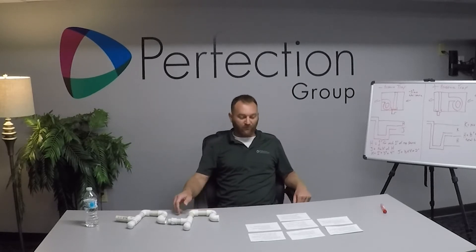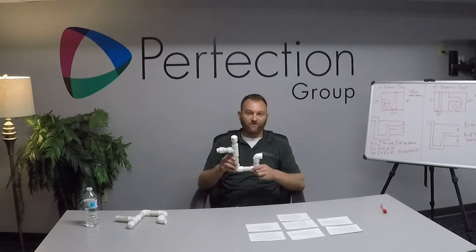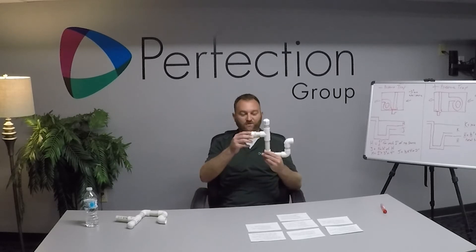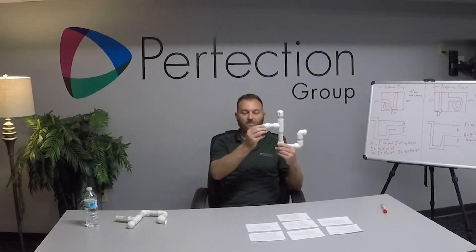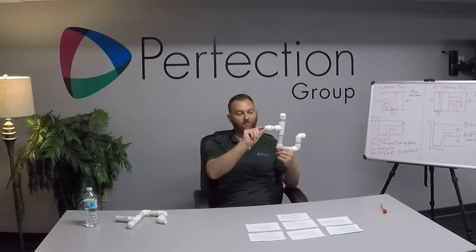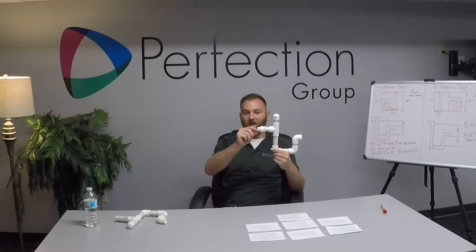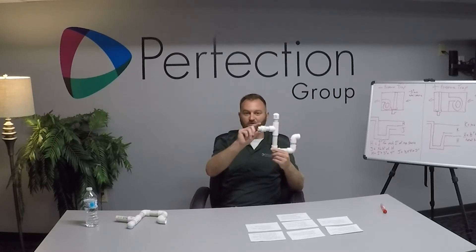Today we will discuss the proper construction of a trap. This is a negative pressure condensate trap. First thing you need to do is make sure you use the appropriate thread compound depending on what your condensate pan has for thread type — steel, copper — just make sure your thread compound is compatible.